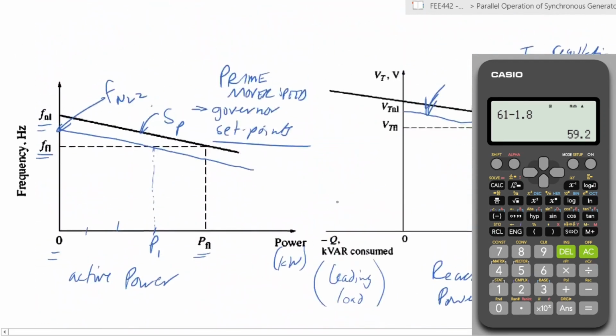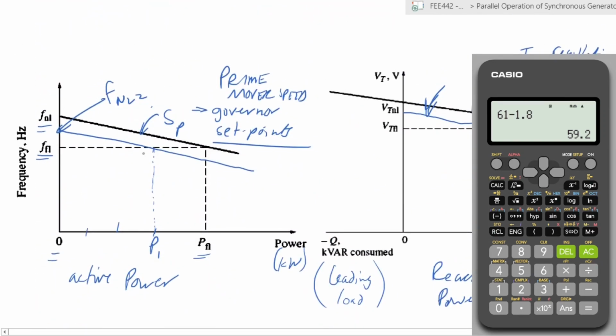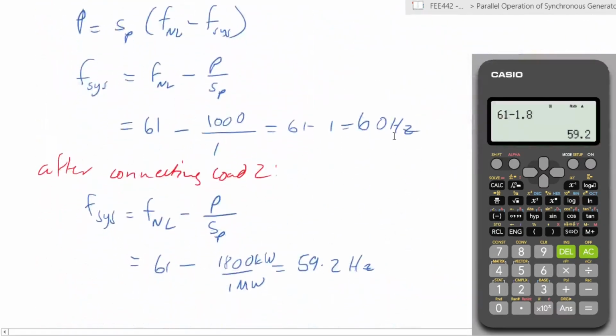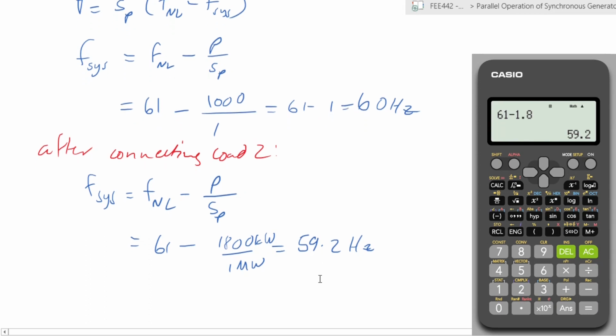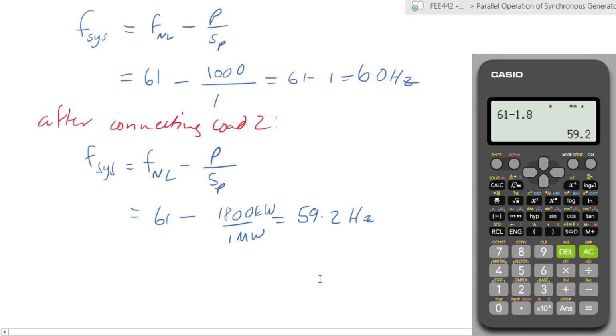So essentially what we've said is you had your initial load over here, but when we connected P1, it traveled backwards and the frequency increased. So the initial one is at this point, and when you add, it now moves down to that point. Say this is P2, right? So there's a drop in frequency from here to here. That's the frequency drop that we've talked about. So from 60 hertz, it has dropped to 59.2 hertz, because for every megawatt increase, it drops by 1 hertz.